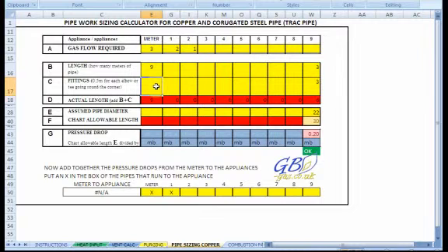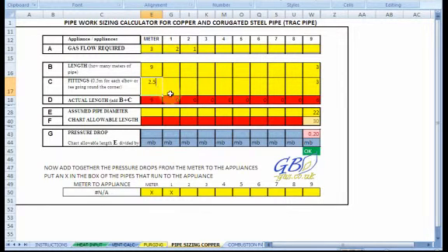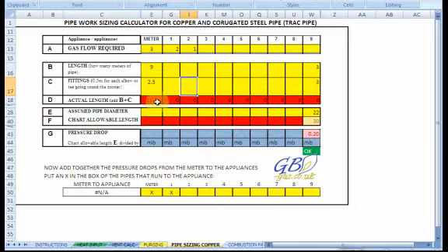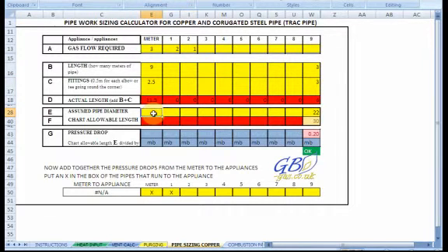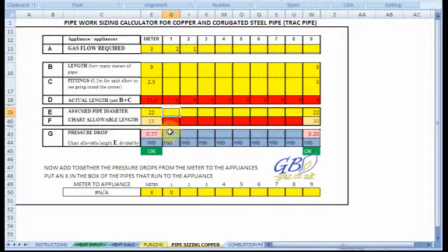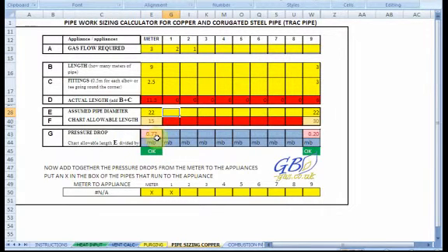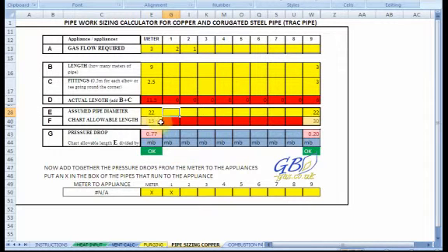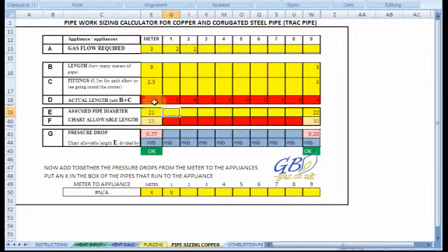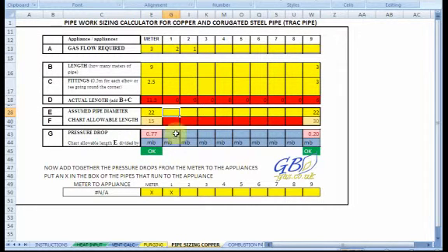Now, five elbows, and or a tee that I'm going round the corner, we always make them half a metre. So, five elbows is equivalent to half a metre for each one, is 2.5 metres. That gives me a total length of 11.5. And if I'm assuming that for this size, I'm going to use 22 millimetre pipe, it will then tell me what my pressure drop would be in the line. Now, for this, my chart allowable length would be 15 metres. I'm only running 11.5, so I've got a 0.77 millibar drop.